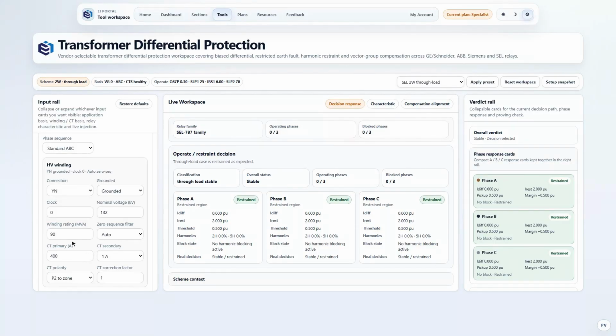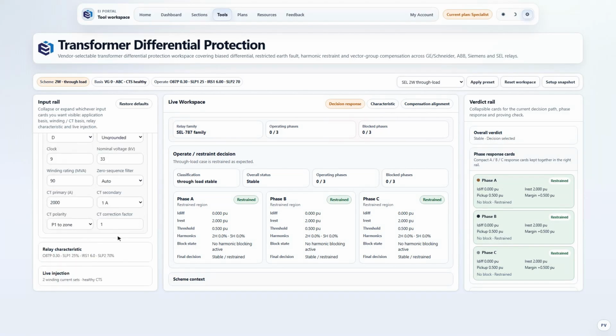And look how deep the input rail goes. Each winding carries its own connection, earthing and clock position, along with CT ratio, polarity, and correction factor. Below that sits zero sequence filtering and a live injection section where every phase current, angle, and harmonic percentage is yours to control. This is a complete scheme description and behavior validation workspace.